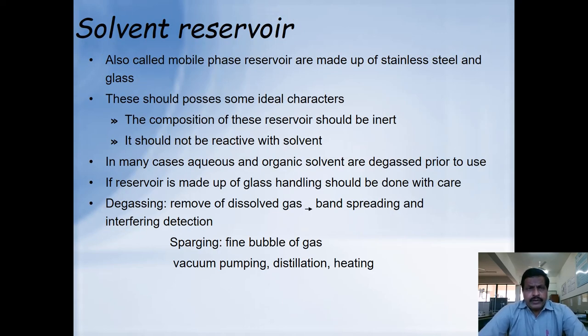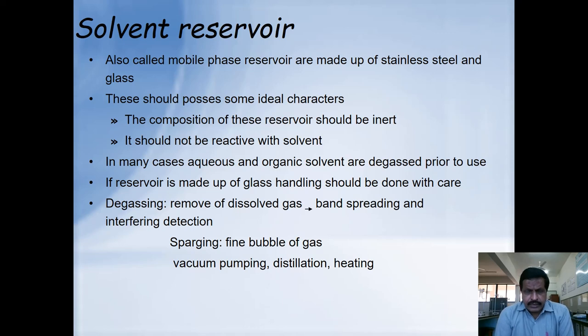The second important component in HPLC is the solvent reservoir, also called the mobile phase reservoir. It is generally made up of stainless steel and glass. The reservoir should be inert and should not be reactive with the solvent used as the mobile phase. In many cases, aqueous and organic solvents are degassed prior to use. If the reservoir is made of glass, you need to take proper precautions and handle with care.